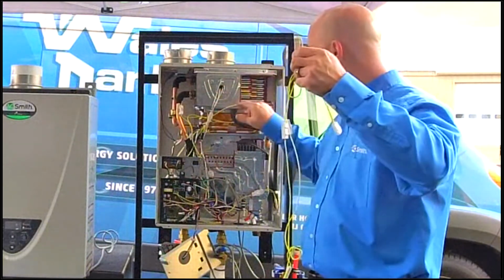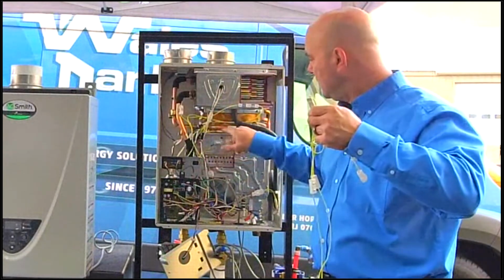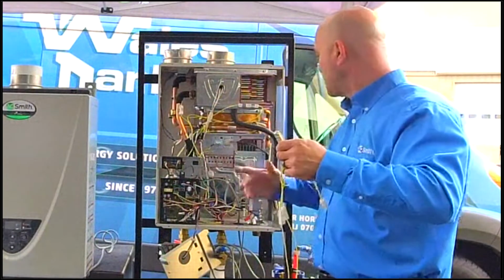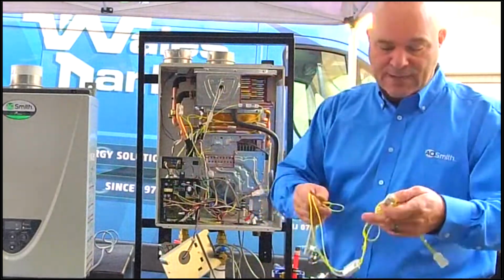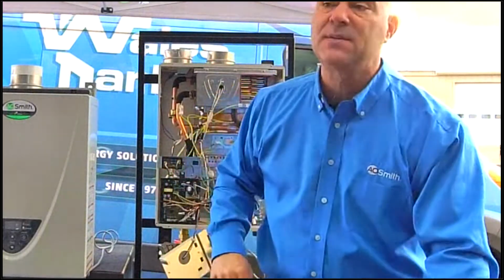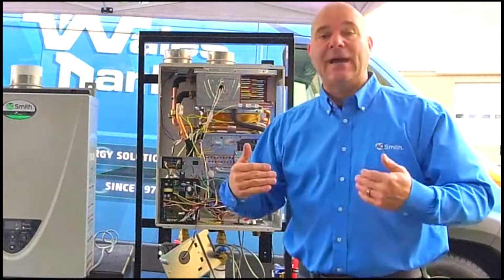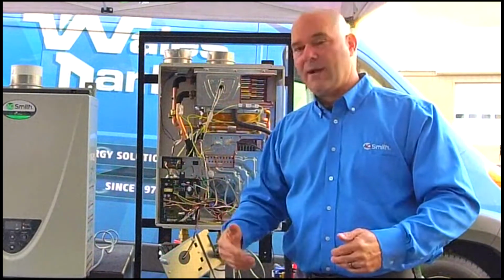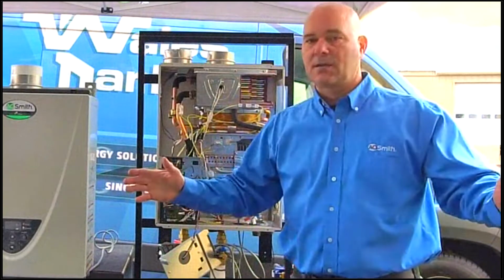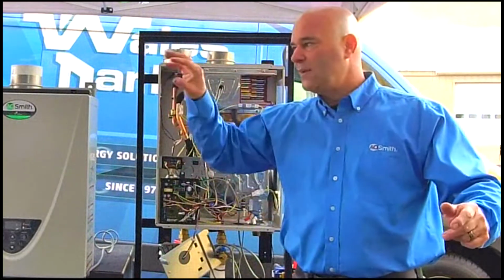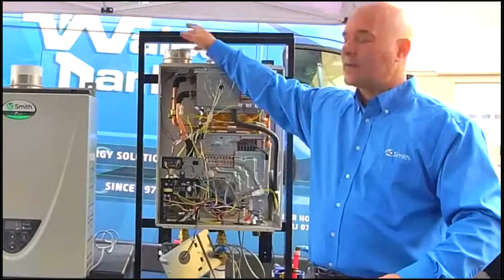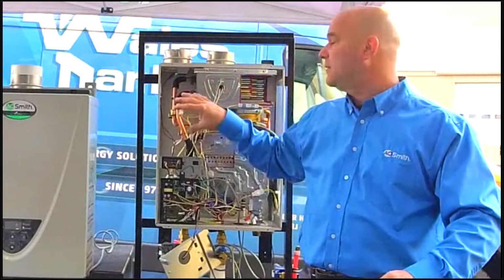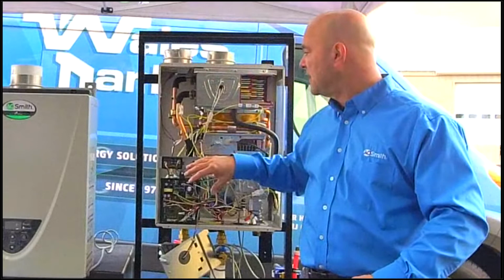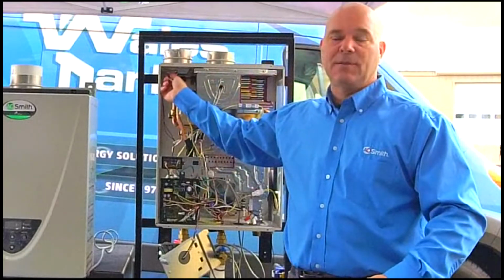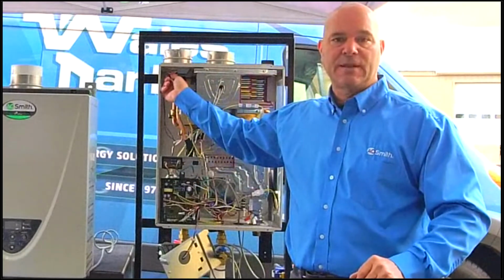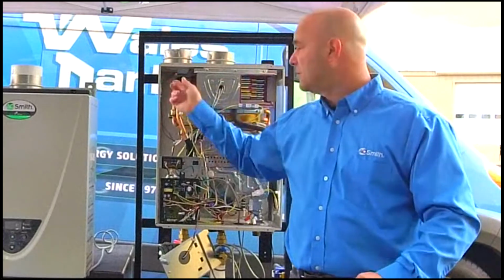Every yellow wire on here, these block heaters, little porcelain heaters, they're all going to turn on, and they're going to trickle some heat into those pipes. If it was colder out, below freezing, that heater is not going to run all day long. And if I have wind pounding on my fresh air inlet, I could be dumping all of that cold air into this chamber of the cabinet, and we're monitoring that. If it gets down below that 36.5, we're just going to make sure we turn that on, keep it a little bit warm, and go from there.